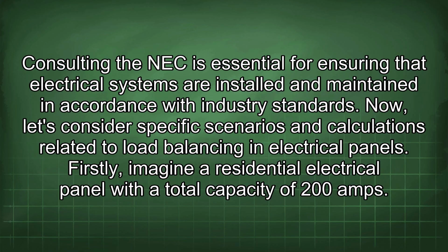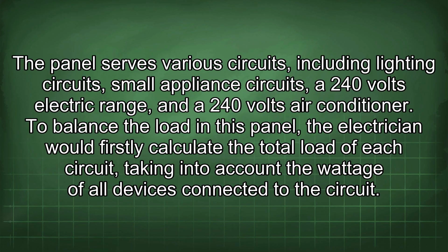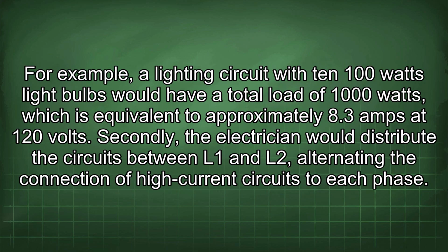Now let's consider specific scenarios and calculations related to load balancing in electrical panels. Firstly, imagine a residential electrical panel with a total capacity of 200 amps. The panel serves various circuits, including lighting circuits, small appliance circuits, a 240 volts electric range, and a 240 volts air conditioner. To balance the load in this panel, the electrician would firstly calculate the total load of each circuit, taking into account the wattage of all devices connected to the circuit. For example, a lighting circuit with 10 100 watts light bulbs would have a total load of 1000 watts, which is equivalent to approximately 8.3 amps at 120 volts.